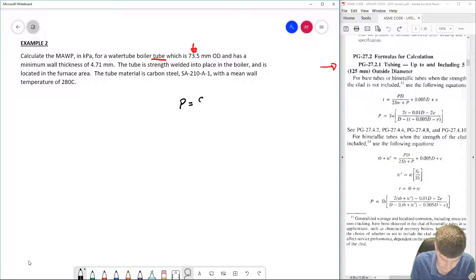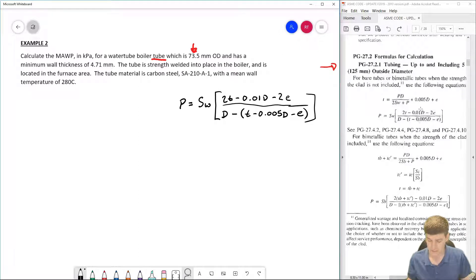So P equals SW times, in large brackets, 2T minus 0.01D minus 2E, all of that divided by D minus T minus 0.005D minus E. Double check my equation again. Just be careful that you don't have mistakes with the decimal places - that's pretty common - as well as the negative signs. We have a whole bunch of negatives on the bottom. Just be careful with that.